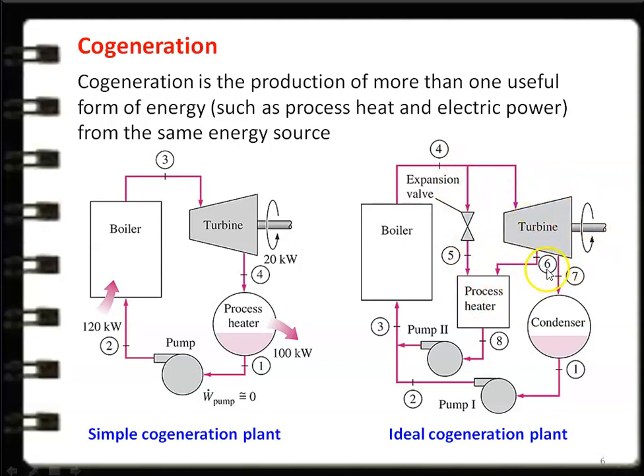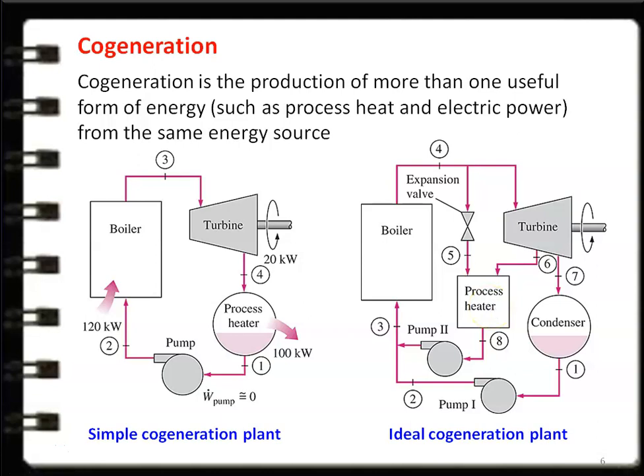In the steam turbine, a small amount of steam is extracted at condition 6 and given to the process heater. The exhaust steam from the turbine goes to the condenser, where it is condensed and recirculated back to the boiler through pump 1. The advantage of the ideal cogeneration plant is that depending on requirements, we can regulate the valve: to produce more power, more steam goes to the turbine and less to the process heater; to produce more process heat, more steam goes to the process heater and less to the turbine.